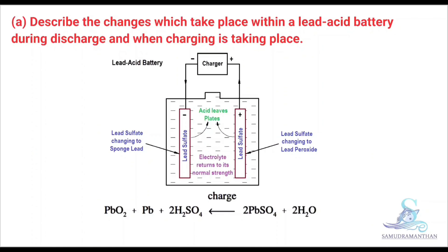This is the diagram of a lead acid battery being charged. On the negative terminal, lead sulphate is changing to sponge lead. On the positive terminal, lead sulphate is changing to lead peroxide. Acid is leaving the plates, the electrolyte is returning to its normal strength, and the reaction is reversed.